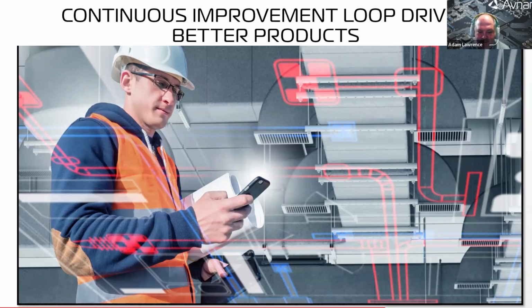So, tying up this section, using the controller's I/O and smarts in manufacturing testing ensures every unit is verified to perform and be safe before it leaves the plant, drastically reducing escapes of defects. It speeds up production and gives you a trove of data for quality control. And more importantly, it doesn't end there. Those same diagnostics continue to serve through the product's life, feeding information back to make the next products even better. It's a holistic approach from cradle to grave, powered by intelligent controls.